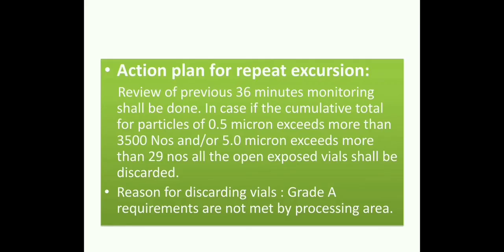In this case, we should review the previous 36 minutes of particle count monitoring. If the total cumulative count of 0.5 micron exceeds more than 3,500 numbers, or for 5 micron if it exceeds more than 29 numbers, then open exposed vials shall be discarded. These figures are the Grade A requirements. Since particle counters work at a speed of 1 CFM air suction, per guideline requirements we must check for one cubic meter, so at least 36 minutes of data shall be reviewed — the 36 minutes being rationalized by a conversion factor between cubic feet and cubic meter.